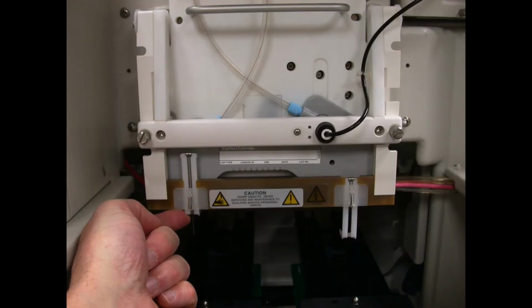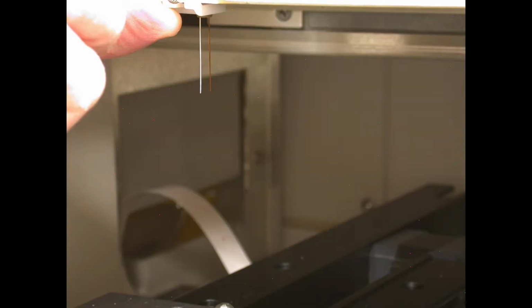The open end of the capillary can be seen by pushing the spring-loaded plastic strip that helps guide the capillary into the vial. One can also see a platinum wire electrode that makes contact with the buffer solution. A similar electrode slides into the buffer on the outlet side of the capillary. When the power is turned on, a voltage is applied between the two platinum wires, and the current is carried by the ions through the solution of the capillary to complete the electrical circuit.